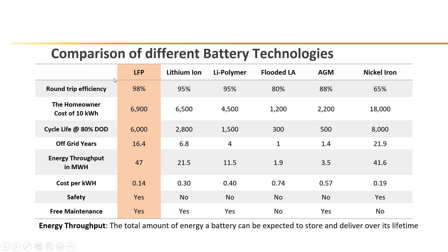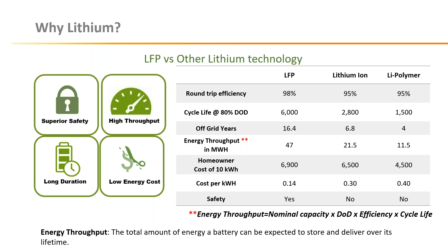Overall, lithium is certainly to be preferred because of the superior safety of the phosphate chemistry, the high energy throughput (47 megawatt hours here), long duration (6,000 cycles at 80% DOD), and the low energy cost. To find energy throughput for other batteries you're considering, take nominal capacity multiplied by depth of discharge, multiplied by round trip efficiency, multiplied by cycle life. Keep that in mind when looking at a battery. Energy throughput isn't discussed much, but it's a good indicator of how long your battery will last and what it will do over its lifetime.